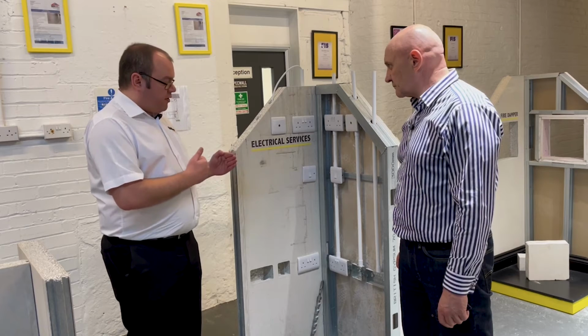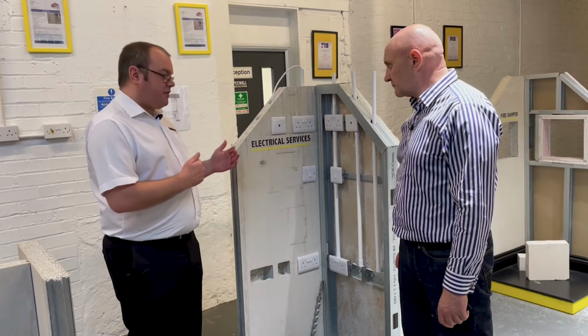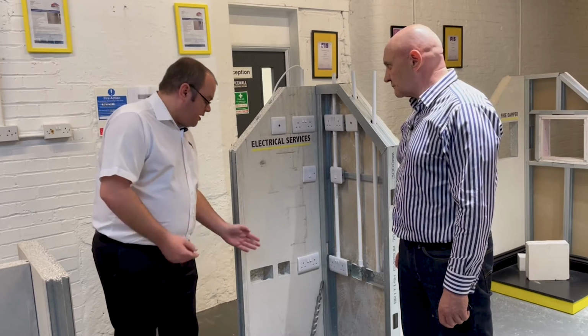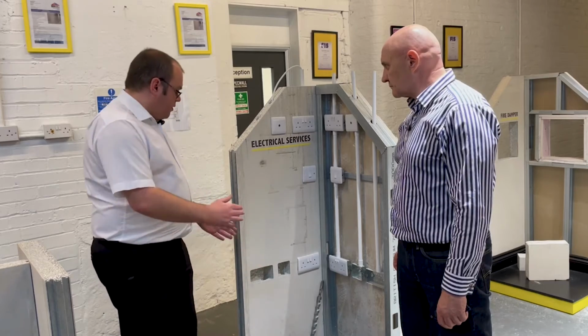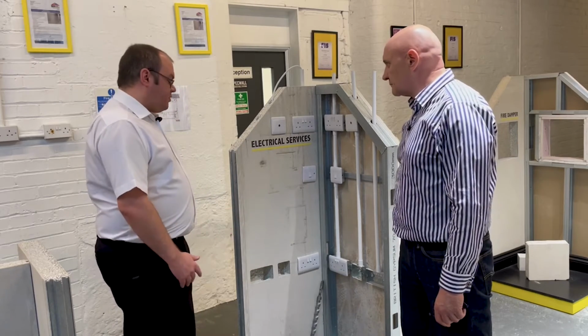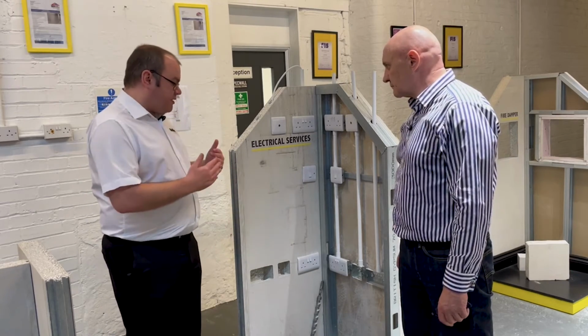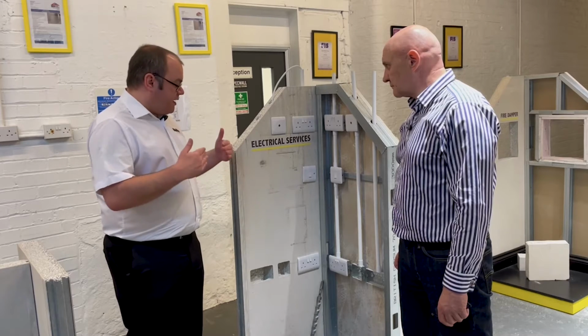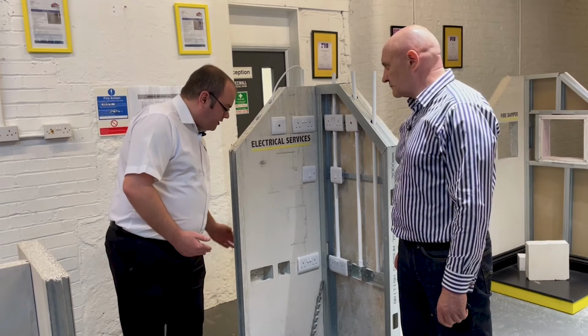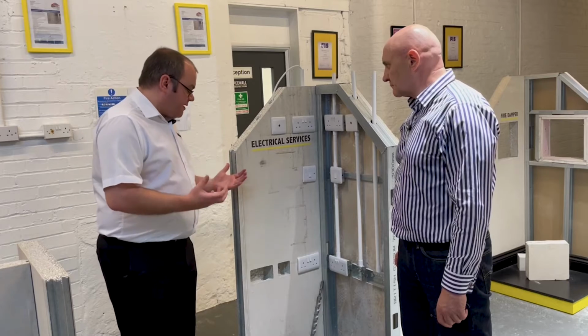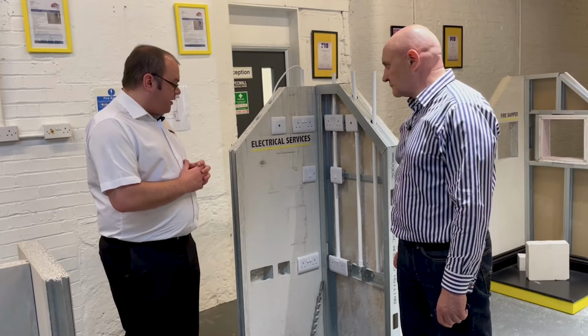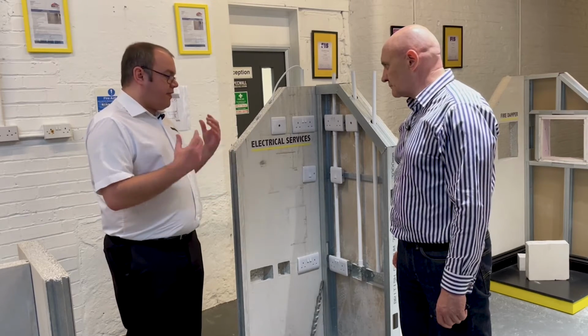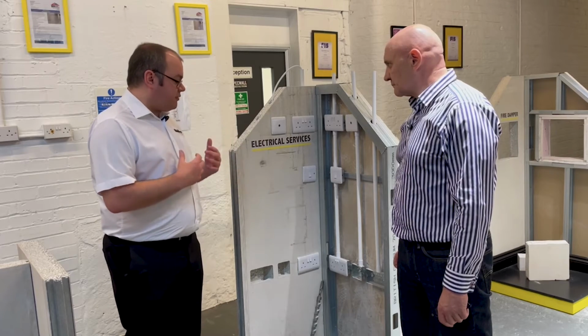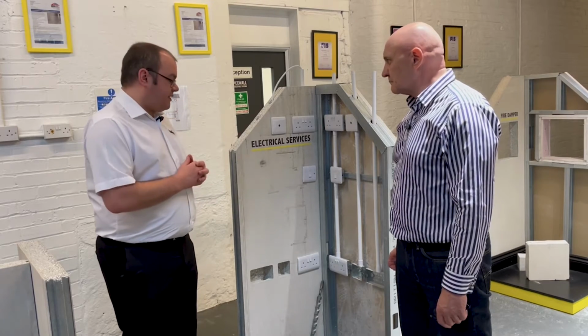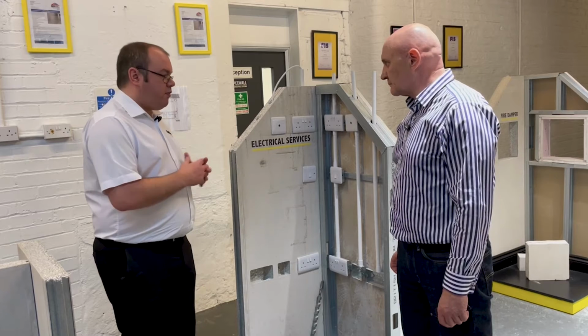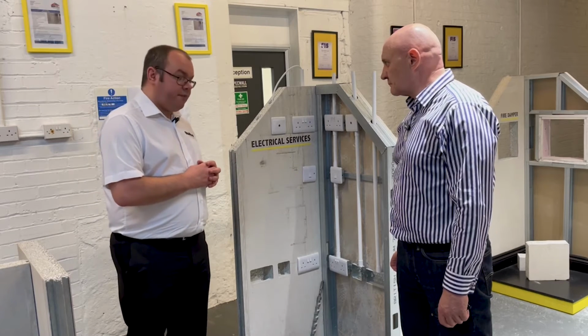Having sockets back-to-back can have a detrimental effect on fire resistance performance, because the metal goes all the way through and allows heat to transfer. Also, from an acoustics performance standpoint, it's much better to have your socket boxes offset slightly. If that's something a project needs to review, get their consultant to reach out to us and we'll share all the primary test evidence so they can assess the application and requirements.